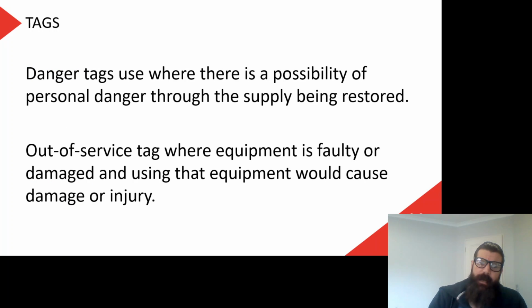So tags. Danger tags are used where there is a possibility of personal danger through the supply being restored. Out of service tags where equipment is faulty or damaged, and using that equipment would cause damage or injury. So whenever we do an isolation and we lock it out, we're going to attach a danger tag to that, so nobody could switch that on and give me an electric shock. We would use an out of service tag if there is a faulty piece of equipment and we need to again isolate that and prevent people from switching it back on because the equipment is broken or hazardous or whatever.